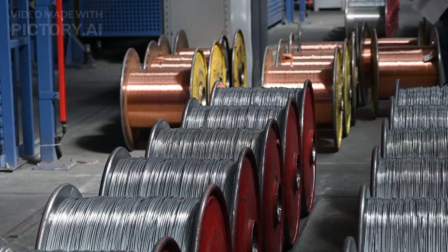1. Determine load requirements. Identify the power, in watts, and the voltage of the load. 2. Calculate load current. Use the formula I = P / (√3 × V × power factor), where I is the current, P is the power, V is the voltage, and the power factor is typically 0.8 for three-phase systems.